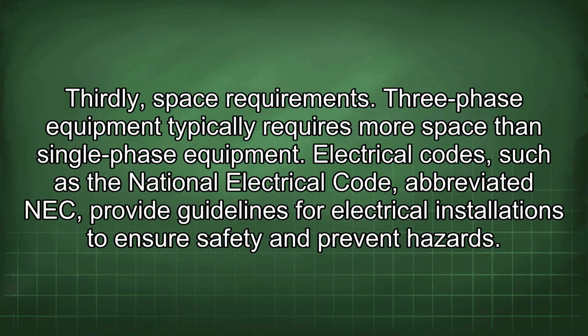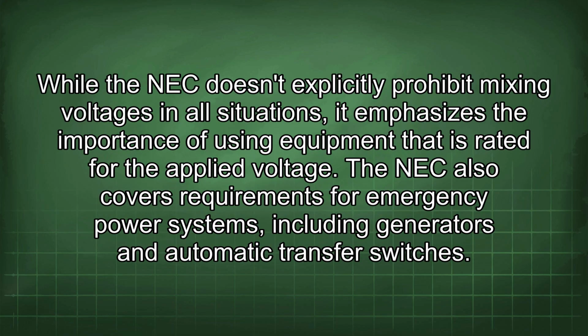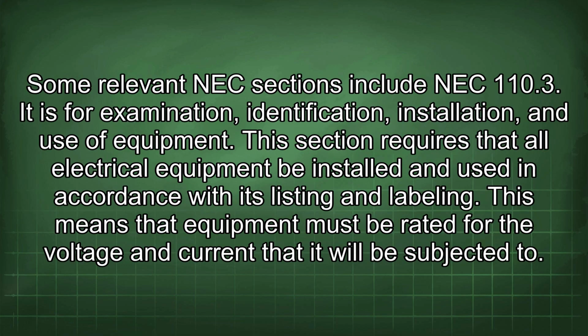Electrical codes, such as the National Electrical Code, abbreviated NEC, provide guidelines for electrical installations to ensure safety and prevent hazards. While the NEC doesn't explicitly prohibit mixing voltages in all situations, it emphasizes the importance of using equipment that is rated for the applied voltage. The NEC also covers requirements for emergency power systems, including generators and automatic transfer switches. Some relevant NEC sections include NEC 110.3. It is for examination, identification, installation, and use of equipment. This section requires that all electrical equipment be installed and used in accordance with its listing and labeling. This means that the equipment must be rated for the voltage and current that it will be subjected to.